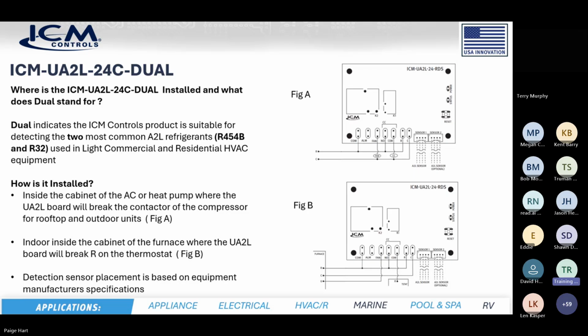So on those models, it's not good enough. There is no compressor or anything you can break. You got to break the thermostat, which will then shut the gas valve off, so you don't have any possibility of ignition in these mildly flammable refrigerants. And then there's a detection sensor that is placed in the equipment based on the manufacturer specifications. So basically, you've got to put that sensor in an area where the refrigerant is going to collect. A lot of times, remember, this refrigerant is heavier than air, so it's going to try to collect in lower areas of the furnace, lower areas of the AC unit and heat pump. So you're going to want to put your sensor in those areas where that refrigerant is going to collect.